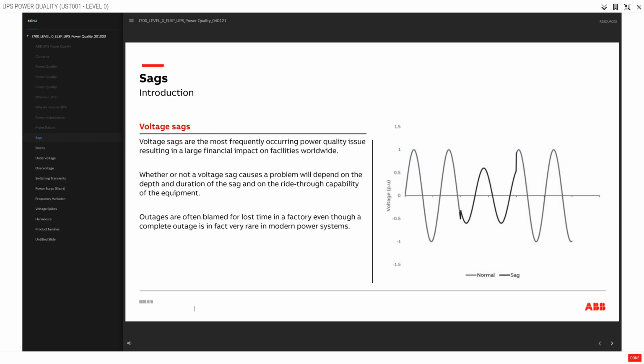Voltage sags. Voltage sags are the most frequently occurring power quality issue, resulting in a large financial impact on facilities worldwide. Whether or not a voltage sag causes a problem will depend on the depth and duration of the sag and on the ride-through capability of the equipment. Outages are often blamed for lost time in a factory, even though a complete outage is in fact very rare in modern power systems.